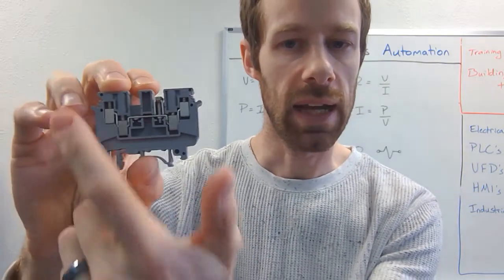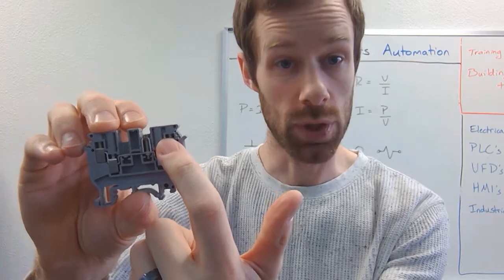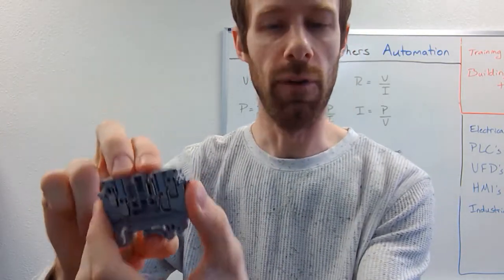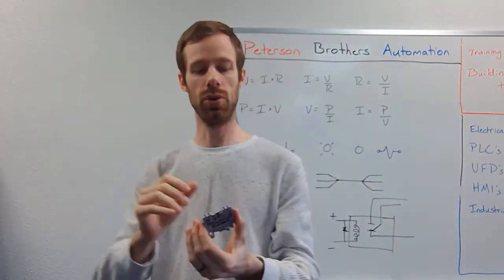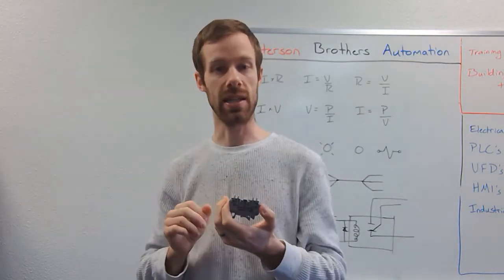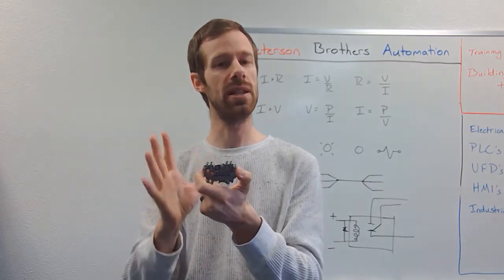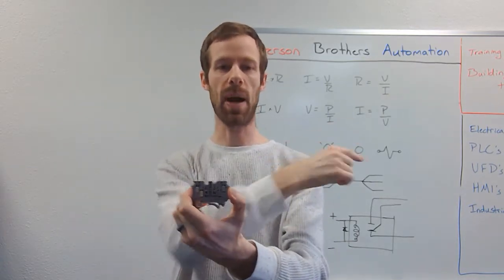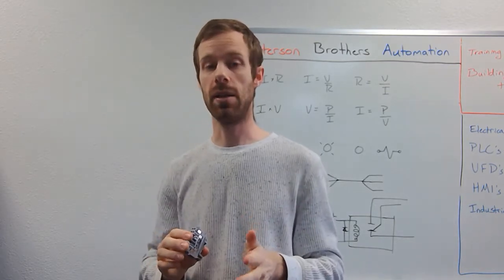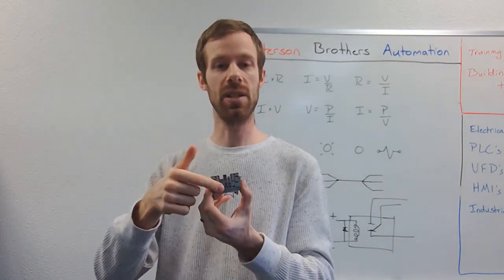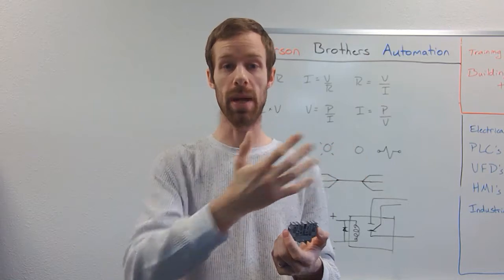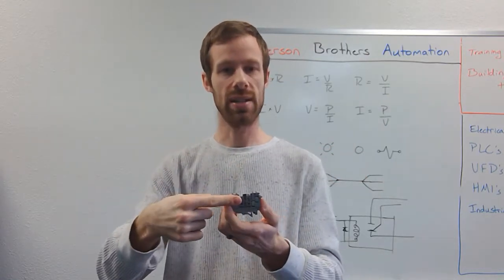So before, I had 4 things all connected together, 4 terminals. Now with this jumper, I have 2 blocks of 4 terminals, which is 8 total terminals that will all be connected together with each other. So if I send power into one of those, I've used up one, it gives me 7 different places left over that I can get that power from. Now, since things are going to be connected in parallel, that means that I could send 7 different load devices their appropriate power as soon as I energize that one wire.